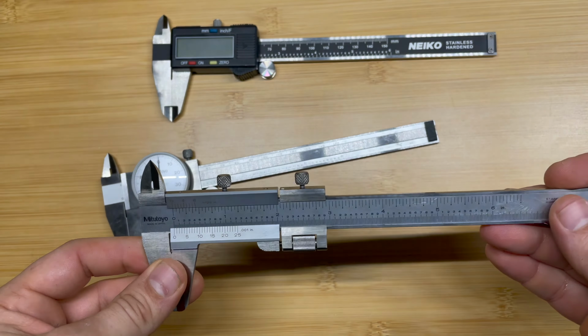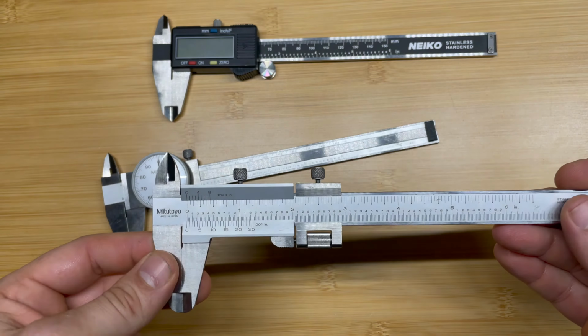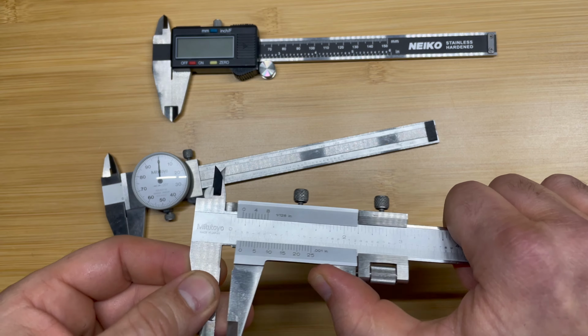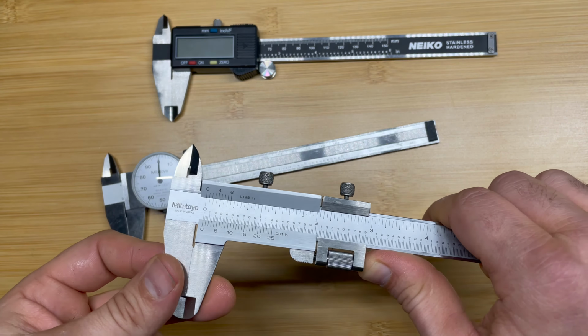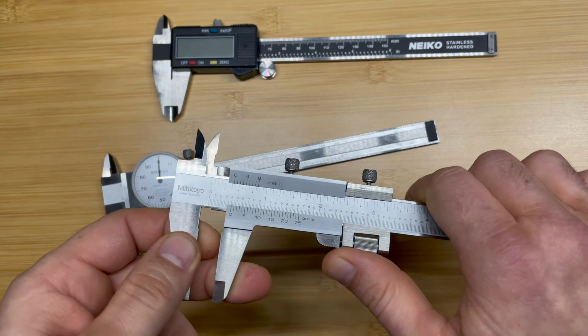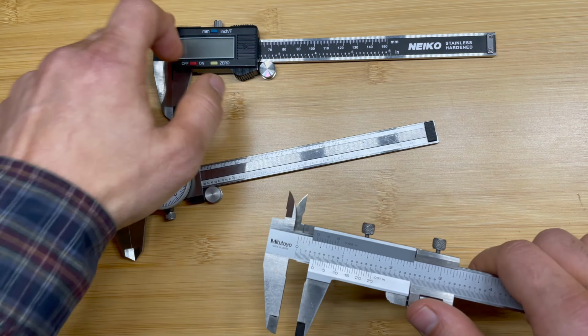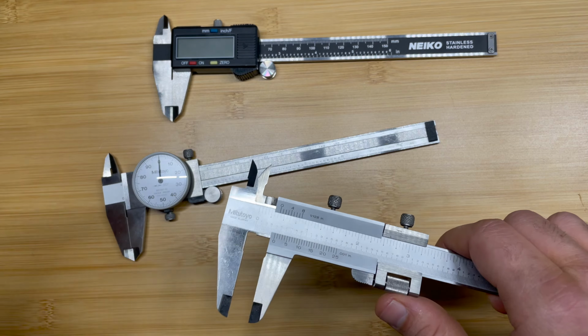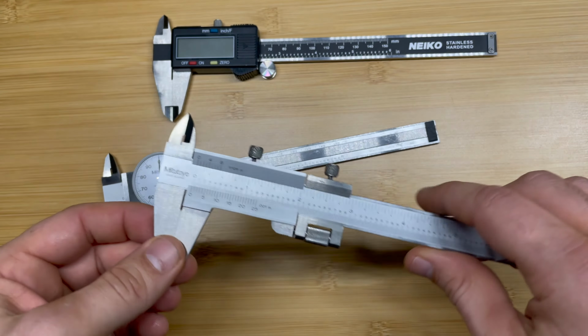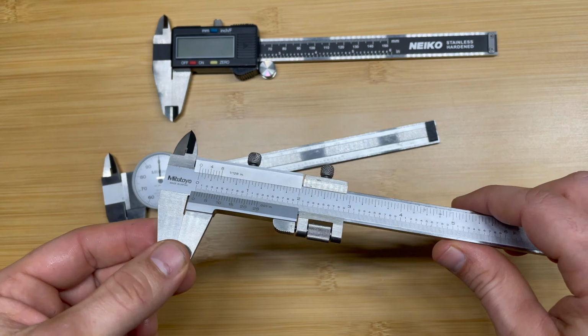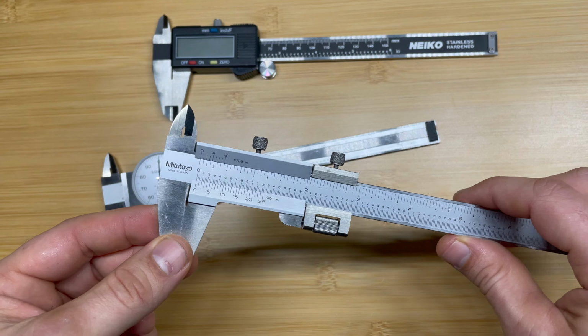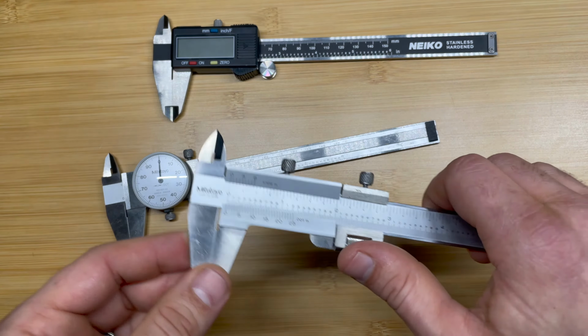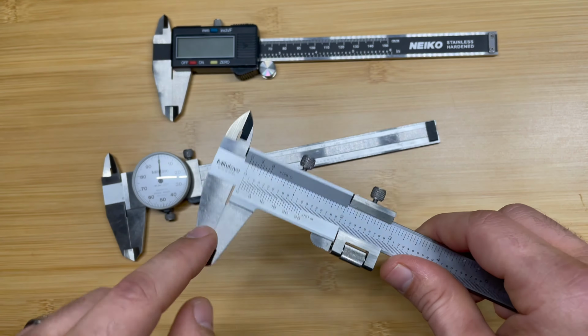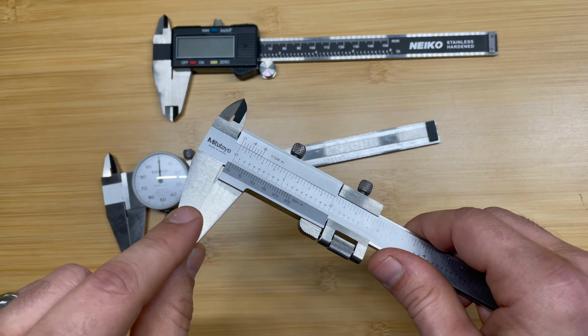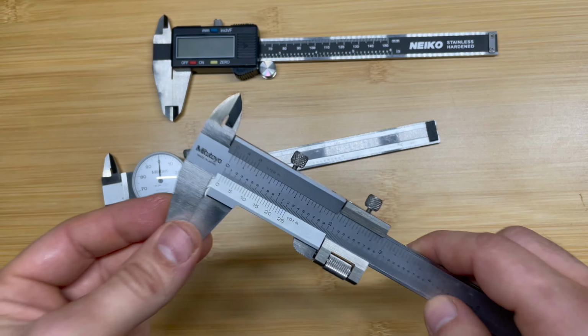The biggest advantage of these things is they're so darn reliable. There isn't a way to change the set point because the set point rarely changes. You'll see with the dial and with a digital caliper, there's a way to zero the device, but with these, unless you really abuse them, you're not gonna knock out the zero point. So, do I think you should buy these or use these in general? I would avoid them if you can.